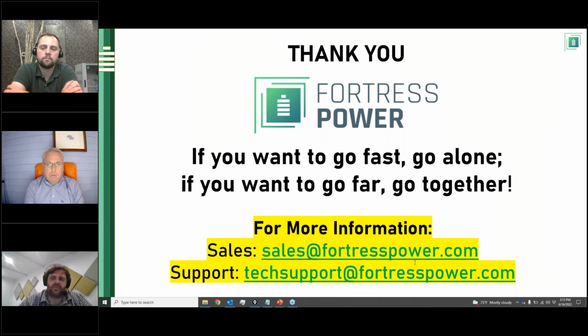So if you get an 8 or 9 kilowatt inverter, you can still use things like your electric tank water heater or 3-ton air conditioner unit and down, but maybe not in an automatic way unless you're buying a smart panel or doing a less budget constrained project by definition. But with our eFlex batteries, on 8 or 9 kilowatts of inverter capacity, or two Easy Solars with 6 kWs and 3 eFlexes, there's really no single load in a house you can't power, provided you have intelligent balance of system design.